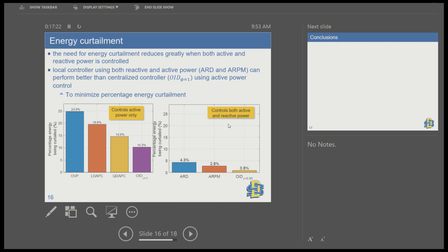Looking at energy curtailment: shutting off the inverter results in about 25% energy curtailment. Droop-based active power curtailment reduces this to around 14.6%, with the quadratic approach performing better than the linear one because marginal curtailment increases with voltage — doing more curtailment near the threshold. With optimal active-only control, curtailment can be reduced to about 10%. But controlling both active and reactive power reduces curtailment to as low as 0.8%, and even local approaches using both active and reactive power can outperform the optimal strategy that uses only active power.